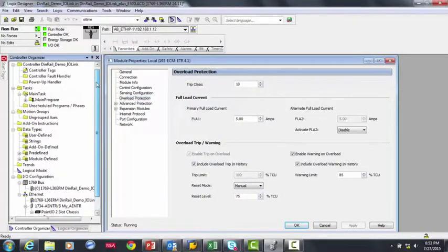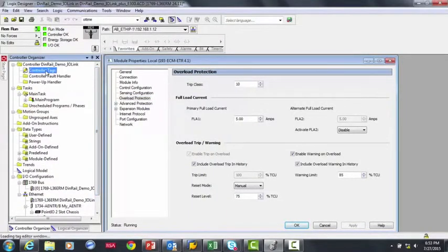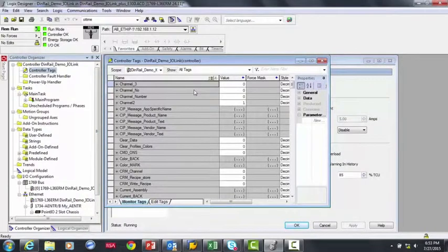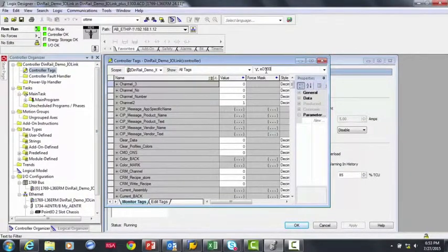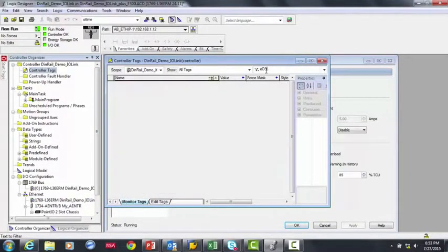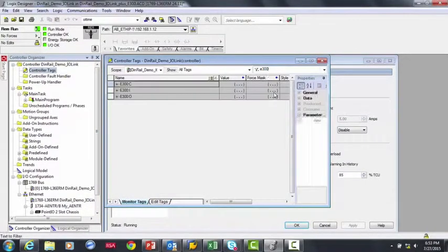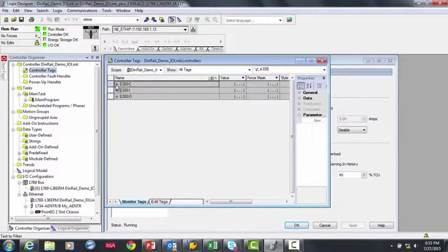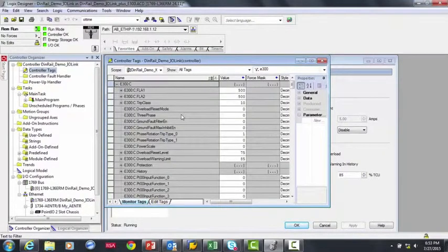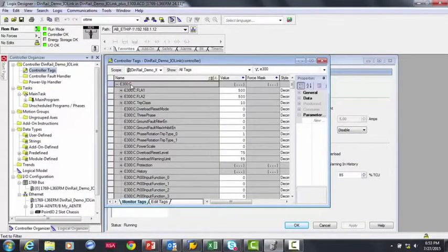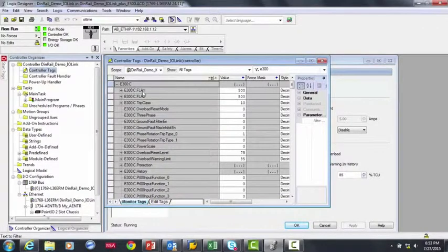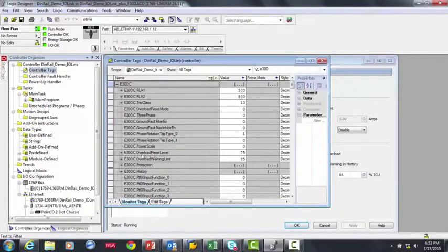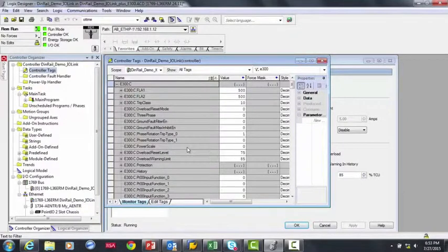Now, if we go to the Device Tags, you can see another nice feature of Premier integration, where all of the device tags for the E300 have logical names. So if we go into the Configuration Tags, you can see Full Load Amperage at 5 amps, the Reset Level, and the Warning Limit again, just like we did in the add-on profile.